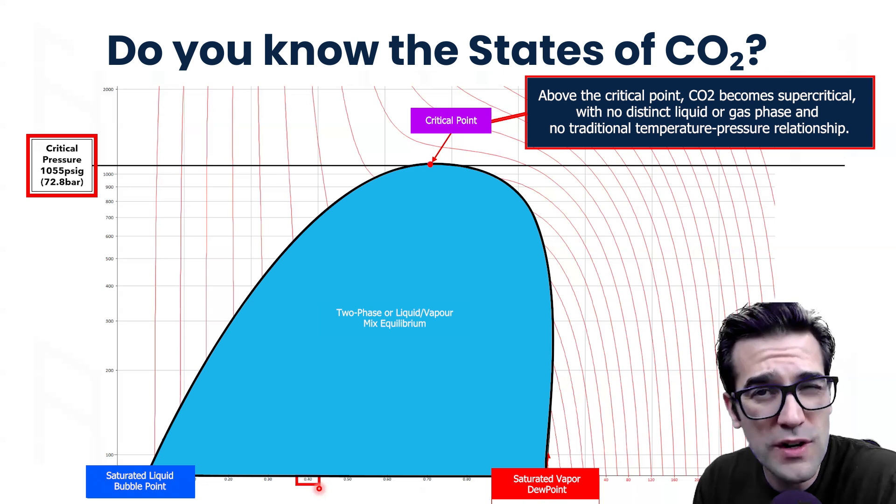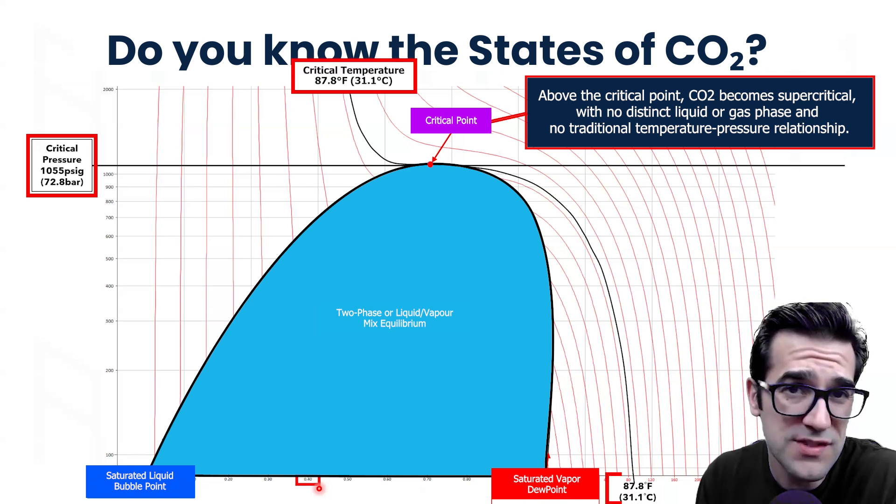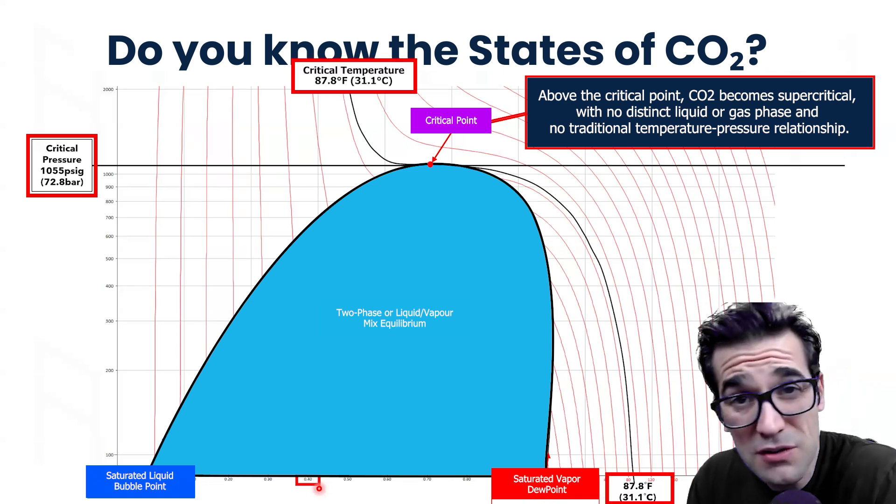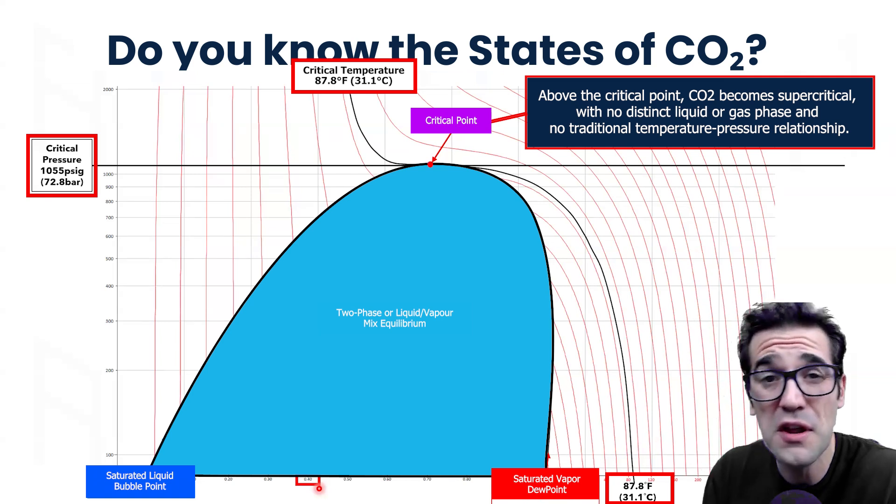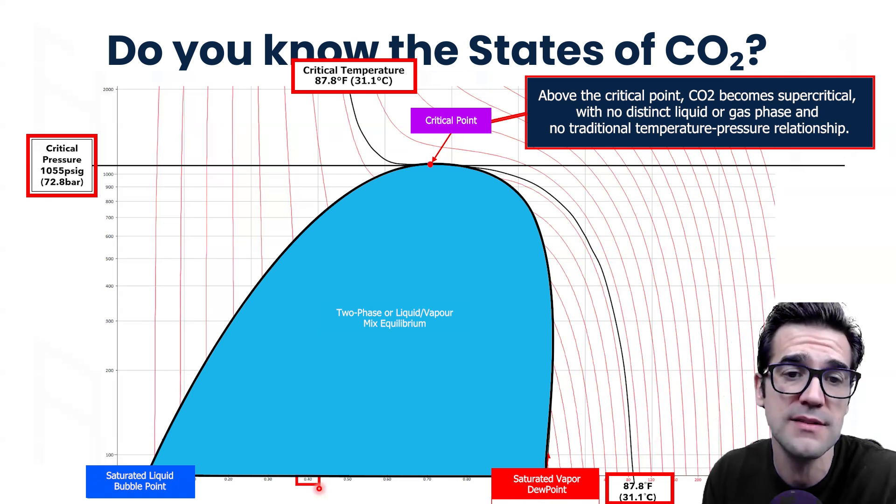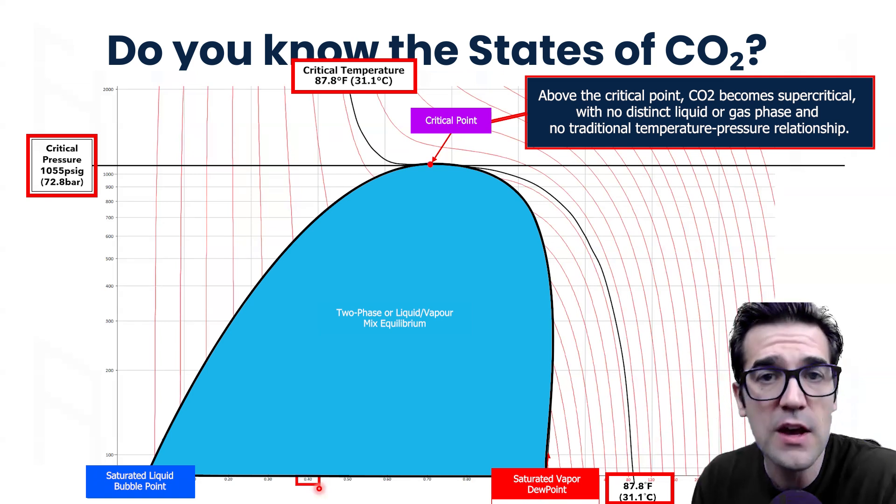Next thing to know is the critical temperature. The critical temperature of CO2 is 87.8 degrees Fahrenheit or 31.1 degrees Celsius. When you're above that, you're above the critical point.